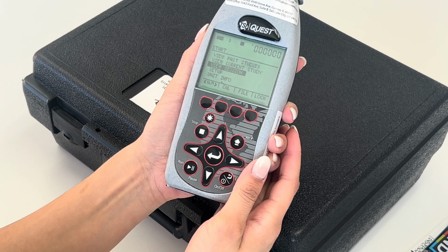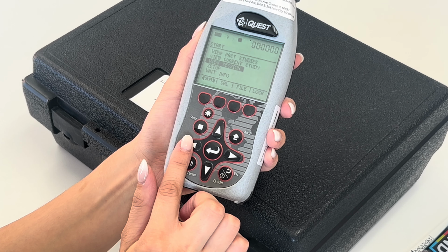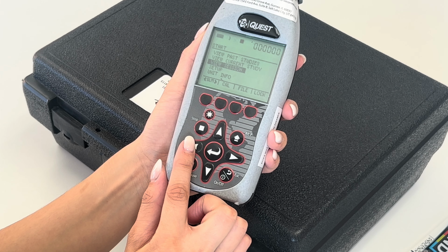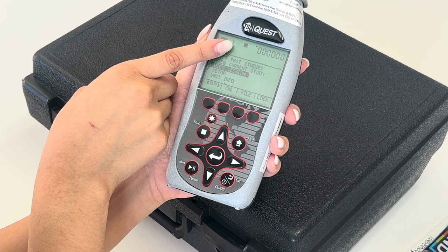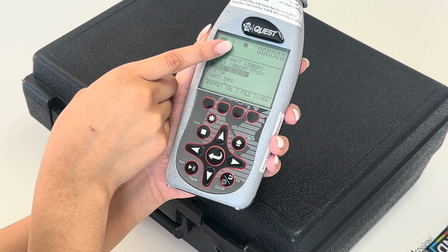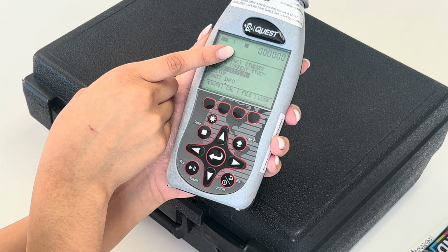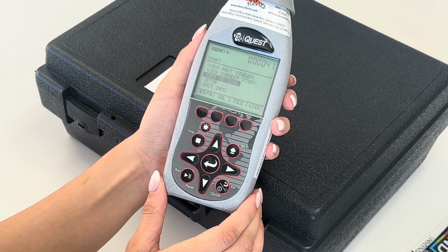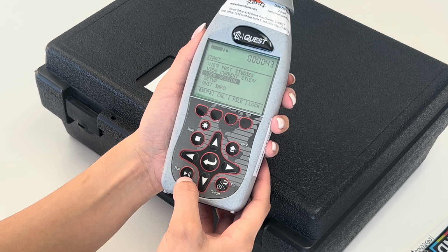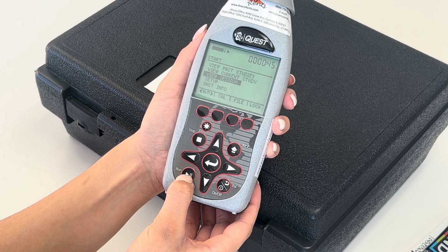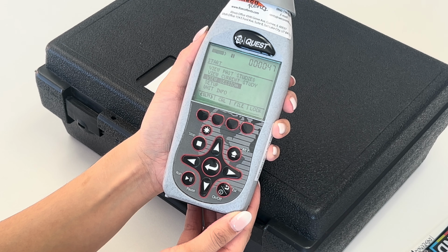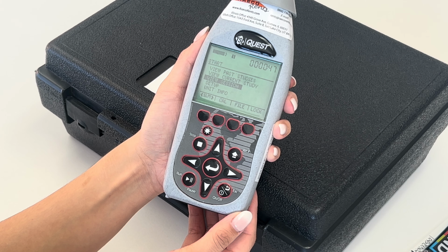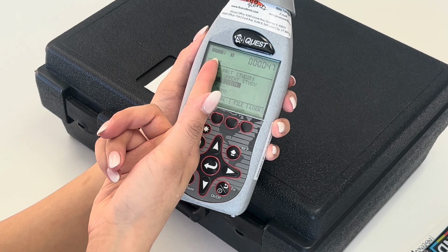Now that we know the functionality of the buttons, let's make sure there is no test being ran. This is important because if the SoundPro is actively collecting data, no settings can be changed. To make sure the unit is stopped, look at the top left corner of the screen, as I am pointing to right now. You should see a battery icon showing the current battery life of the device and a play, pause, or stop icon. As you can see, a study was being ran, so I paused it by using the run/pause button at the bottom of the screen.